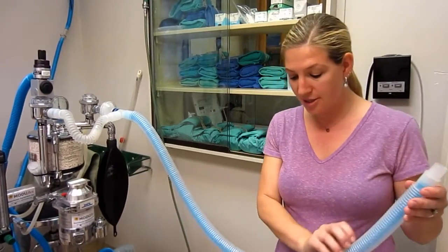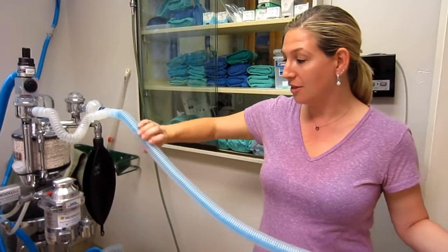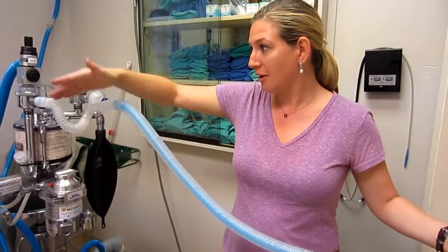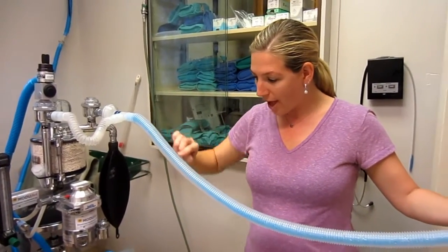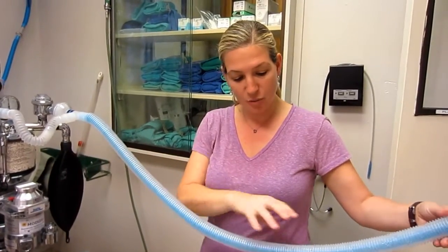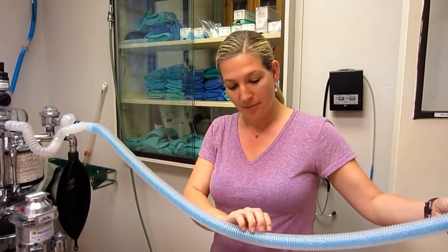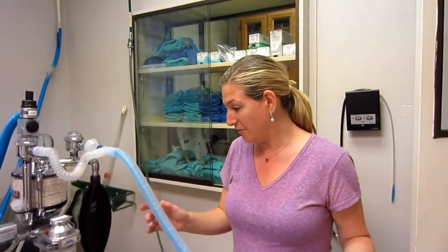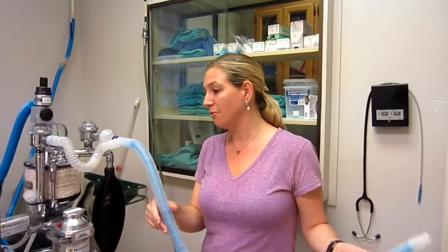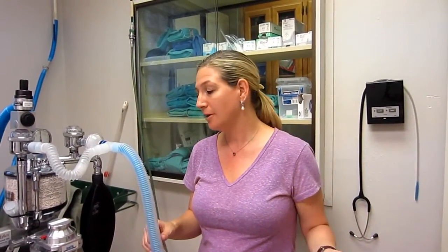And it runs down the outside of the tube and into the exhalation valve. But what happens to that inside tube is this warm, moist gas mixture is running down the tube, and it's warming what's inside of the inhalation tube. So I just find this a very fascinating tube, and it also helps keep the warmth and the moisture in the patient. So I find it to be a great benefit to use these.